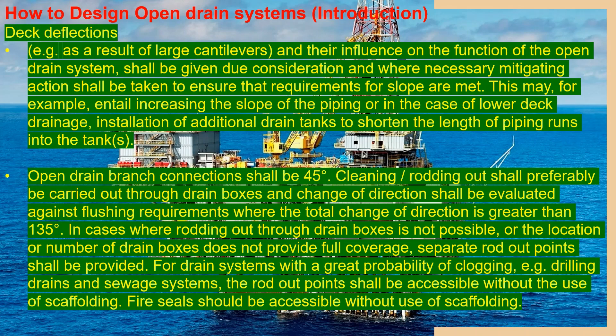In cases where rodding out through drain boxes is not possible, or the location and number of drain boxes does not provide full coverage, separate cleanout points shall be provided for drain systems with a high probability of clogging, such as drilling drains and sewage systems. All cleanout points shall be accessible without the use of scaffolding; fire cells should also be accessible without use of scaffolding.